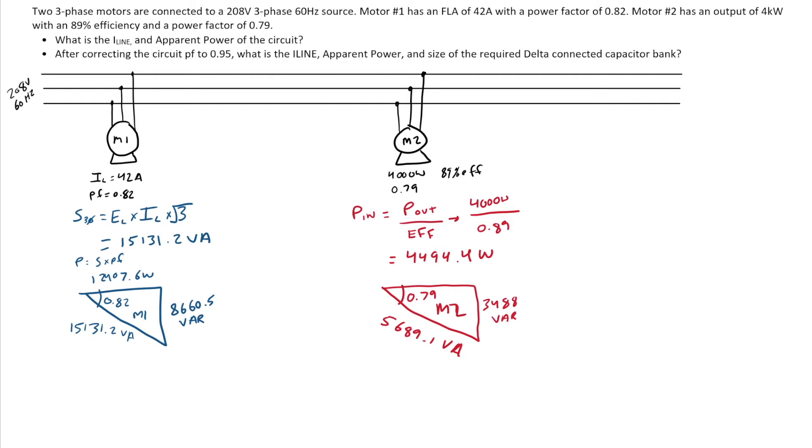Now what I want to do is I want to combine those two motors to make a total. So what we know when we're calculating our total is that the power total is equal to power of motor one plus the power of motor two. Our watts will add up. So I add up 12,407.6 plus 4,494.4, and I get exactly 16,902 watts.